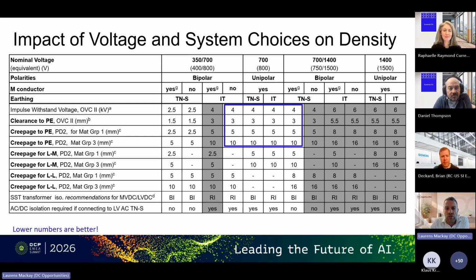If you go to a higher voltage, you need a higher clearance as well. Now the interesting part is that these four highlighted systems have all the same requirements for clearance and creepage. So as soon as you consider a floating IT grounded system or high impedance grounded system, you need extra clearance to get the 700 or 800 volts to ground. But looking at the rightmost highlighted column, to get to 1500 volts, the low voltage limit, we can already do that with the same clearances we're considering for the unipolar 800 volt floating systems.